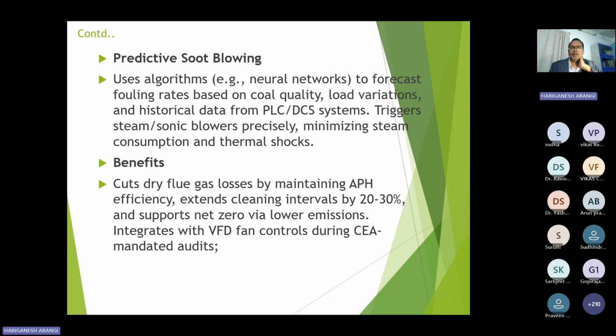Predictive soot blowing uses algorithms to forecast fouling rates based on coal quality, load variations, and historical data. Because all coals are not the same. Mostly Indian coals have a higher percentage of ash, whereas Indonesian or South African coals have less ash and higher calorific value. If the ash percentage is more in the coal itself, that ash will accumulate in the boiler also.